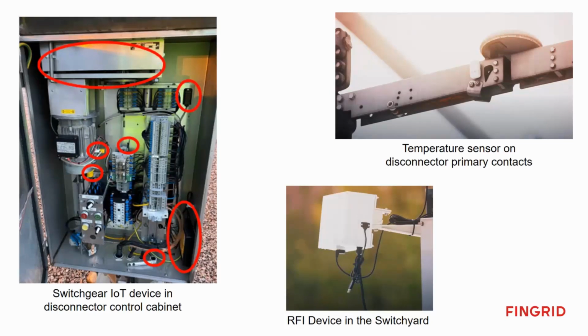And then on top right we can see one small white temperature sensor attached on the primary parts of the disconnector to measure the temperature in the primary contacts. So if we have some loose contact or loose joint somewhere, we can detect the increased resistance by measuring temperature, because they tend to overheat in this situation.